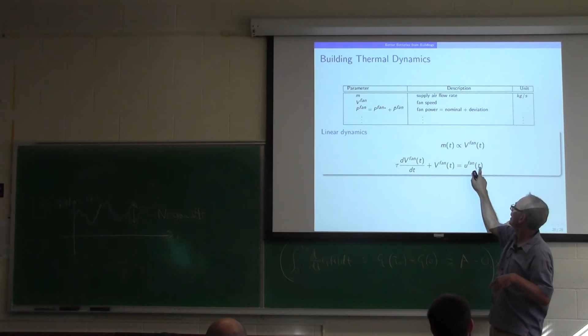Now here's where things get kind of tricky. We've got the supply airflow rate, which is something building operators want to control, and that's roughly proportional to the fan speed. Of course, there's dynamics there, and the speed of the fan follows dynamics according to our set point. So there's a knob on this variable speed drive. If we turn it instantly, the fan doesn't instantly change - it's a low-pass filter. And we can get this model.